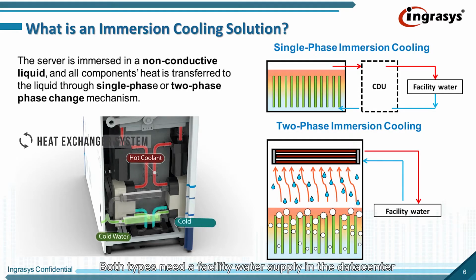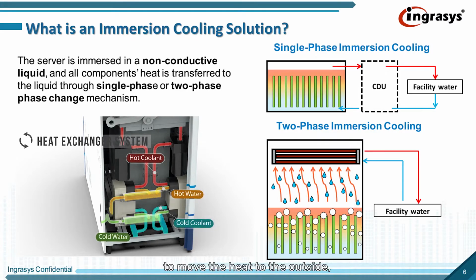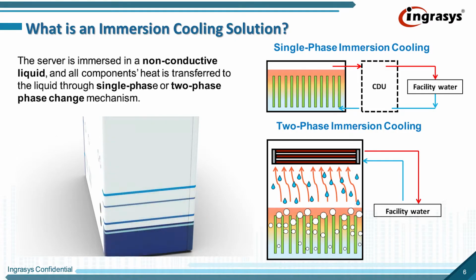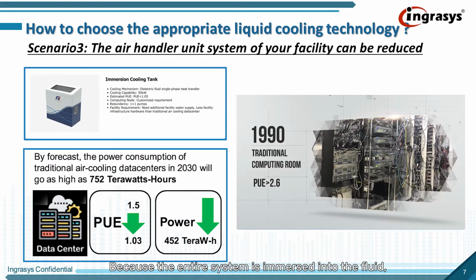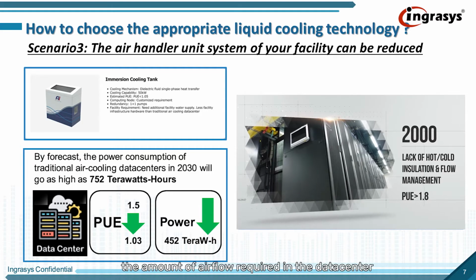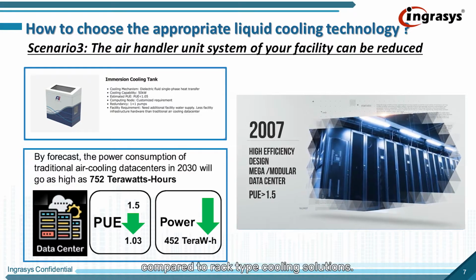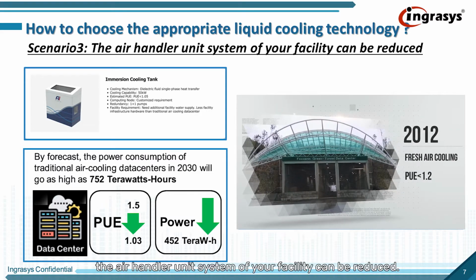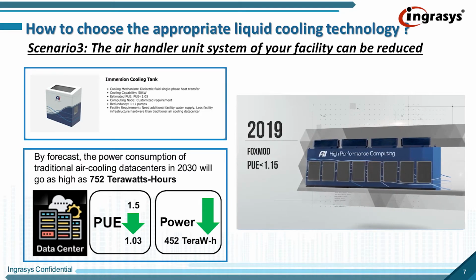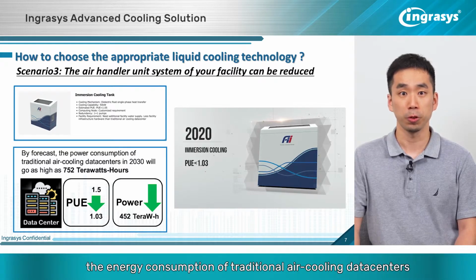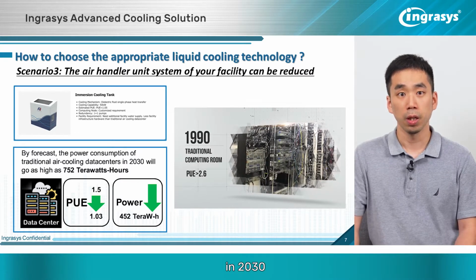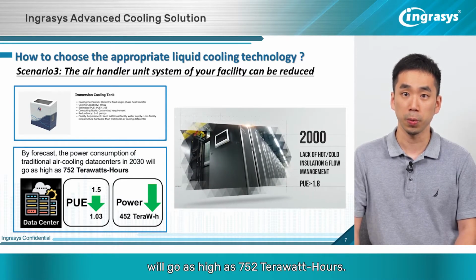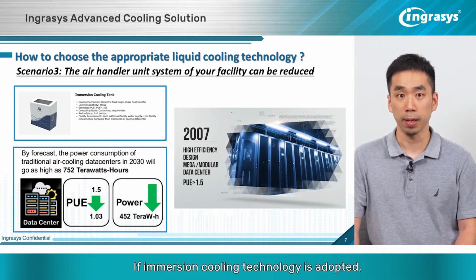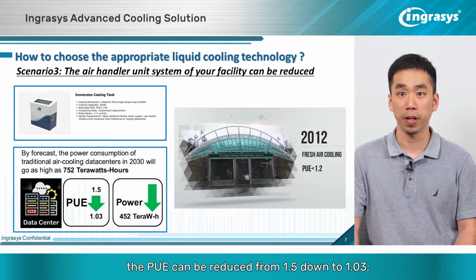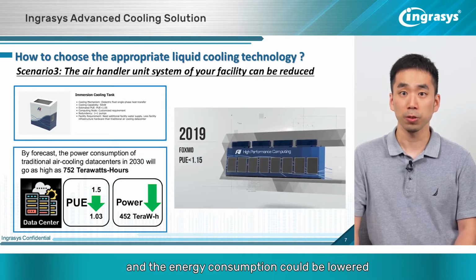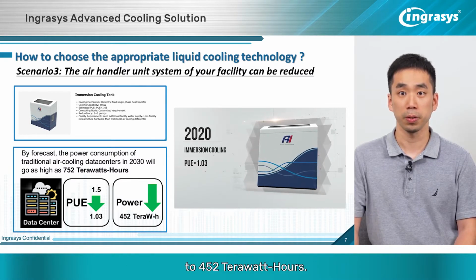Both types need a facility water supply in the data center to move the heat to the outside, like the liquid-to-liquid rack solution. Because the entire system is immersed into the fluid, the amount of airflow required in the data center is greatly reduced compared to rack-type cooling solutions. Thus, the air handler unit system of your facility can be reduced. By forecast, the energy consumption of traditional air cooling data centers in 2030 will go as high as 752 terawatt-hours. If immersion cooling technology is adopted, the PUE can be reduced from 1.5 down to 1.03, and the energy consumption could be lowered to 450 terawatt-hours.